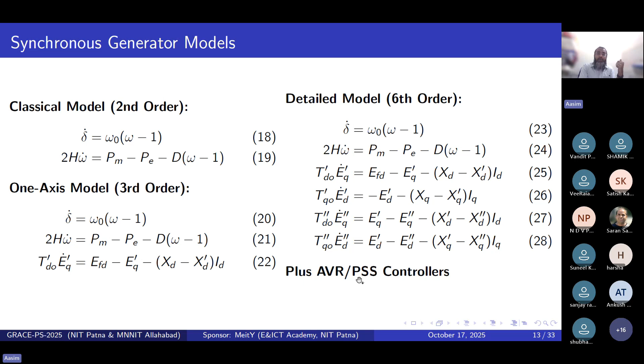For more detailed transient behavior, we use a detailed, sixth order model. And if we go even higher, to study fast voltage regulators, power system stabilizers, or controllers, additional states get added — for a single generator, that's 6 states plus AVR and PSS states, at least one or two more.